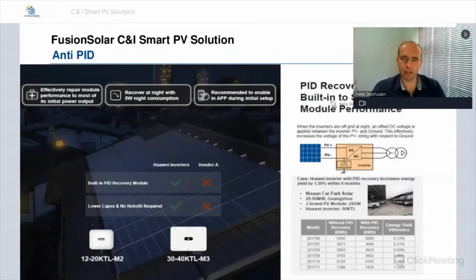So the PID recovery is built in to secure better module performance. When the inverters are off-grid at night, an offset DC voltage is applied between the inverter PV negative and ground. This effectively increases the voltage of the PV string with respect to the ground. In a case study, a Huawei inverter with PID recovery increased energy yield by about 1.59% within 6 months. In the table below, you can see the test that was done: this is the normal system setup without PID recovery, and this is the setup with PID recovery. You can see that the difference in yield is increasing over time instead of decreasing.